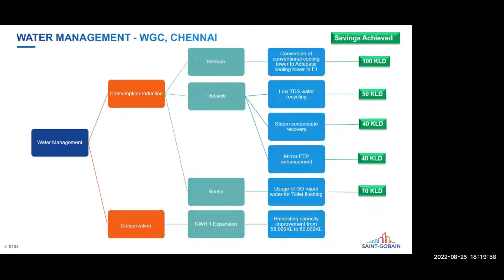Then this is one of the major projects which we have done in our float one cooling tower. The cooling water system is a major, critical system in float glass manufacturing. Earlier we used this conventional cooling tower, shown in the before picture on the left side. In this cooling tower, the main disadvantage is the evaporation loss. Around 100 to 150 KL of cooling water gets evaporated, and daily we have to top up 100 to 150 kiloliters of water.